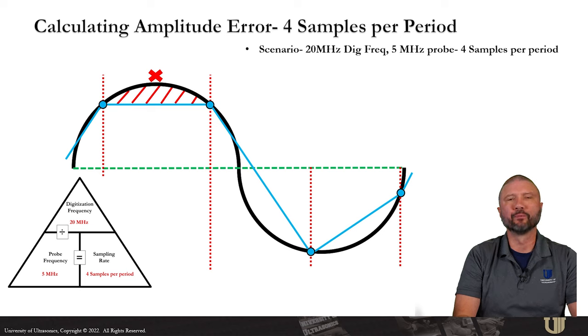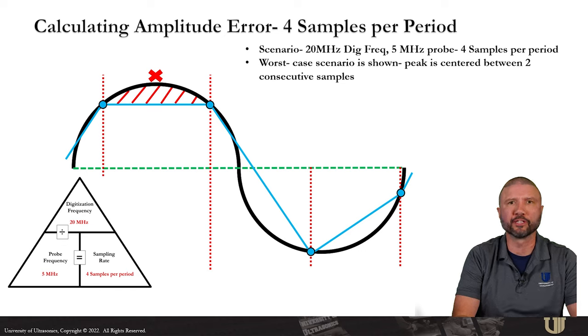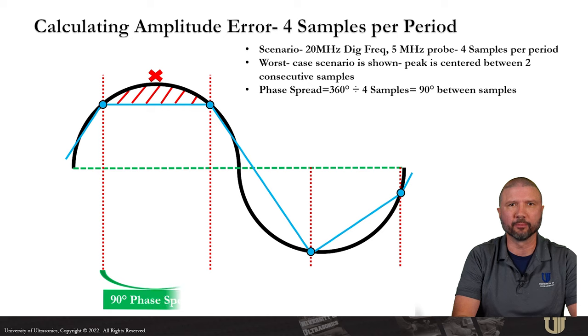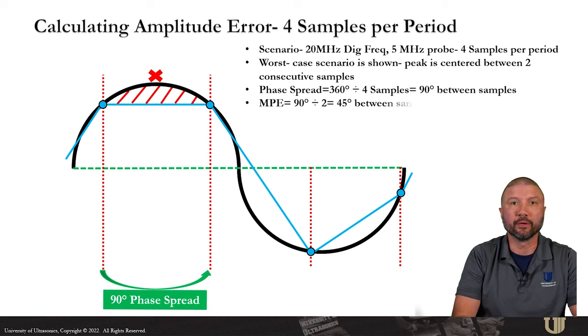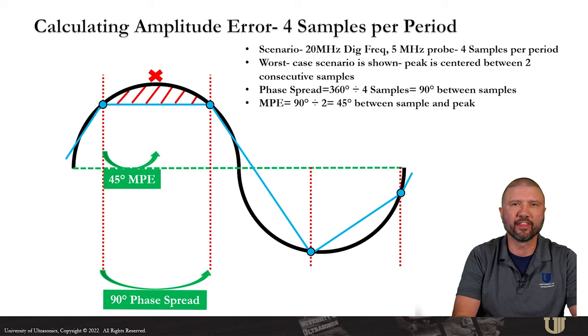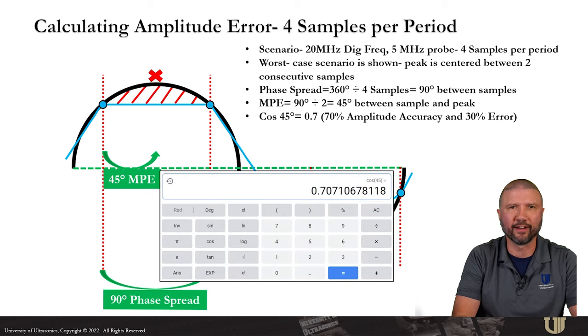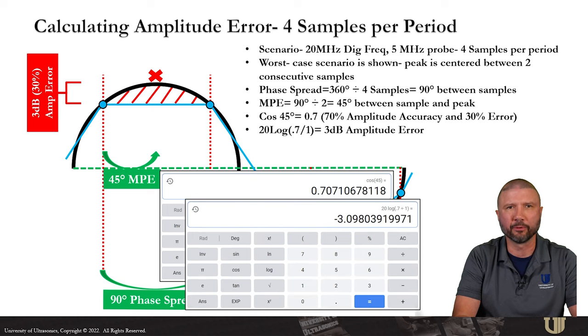Let's look at another scenario. 20 MHz digitizing frequency, 5 MHz probe resulting in four samples per period. The worst case scenario is shown where the peak is centered between two consecutive samples. My phase spread can be calculated to 90 degrees between samples. And if I divide that by two, I've got 45 degrees between the sample and the peak. Cosine of 45 is 0.7, which means we have 70% accuracy, 30% error. And then if I convert that to a dB, I can show three dBs of amplitude error.